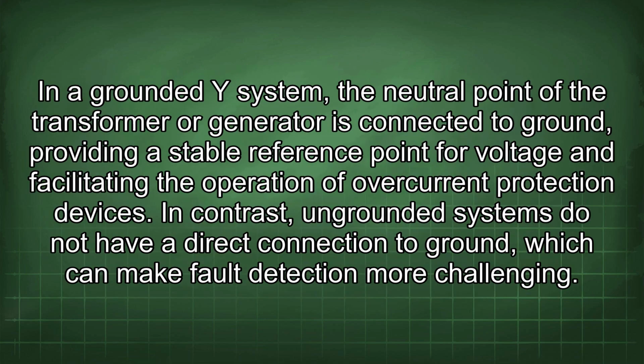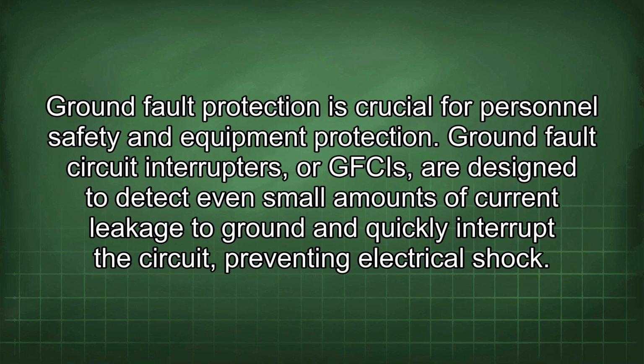In a grounded Y system, the neutral point of the transformer or generator is connected to ground, providing a stable reference point for voltage and facilitating the operation of overcurrent protection devices. In contrast, ungrounded systems do not have a direct connection to ground, which can make fault detection more challenging. Ground fault protection is crucial for personnel safety and equipment protection.